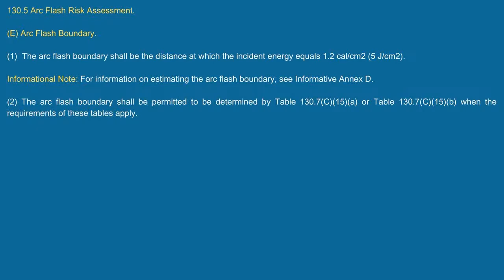Question: is there any correlation between the arc flash boundary and the working clearance? No, nothing. The working clearance is specific to the NEC as an installation requirement. It's not for the arc flash boundary. Those clearance distances protect you from shock, so you can't be standing somewhere and reach behind you and create a touch and step potential. That's what it's for. I know someone who said otherwise in one of his videos, and he was wrong, and I called him out on it, and he didn't even reply.